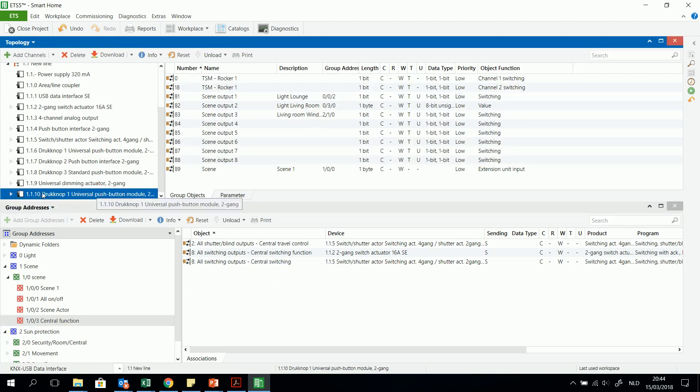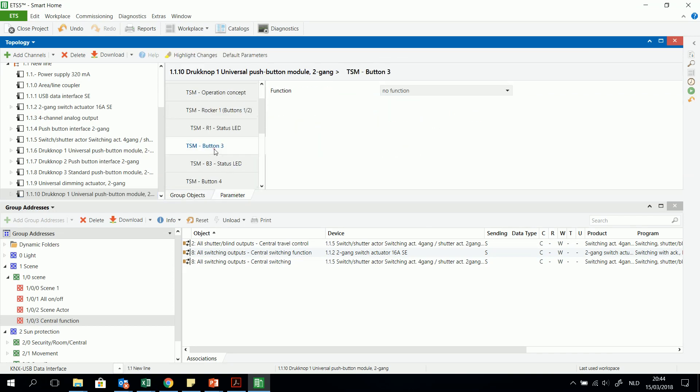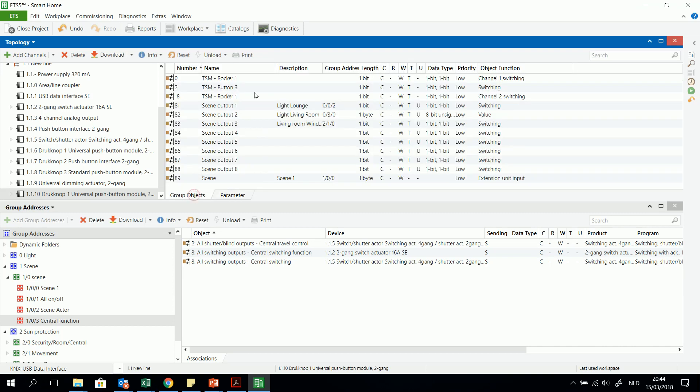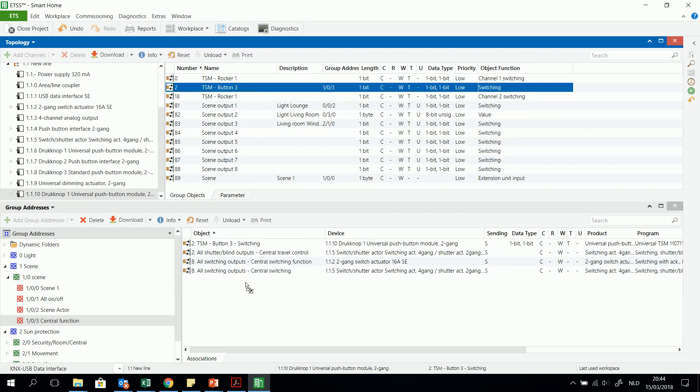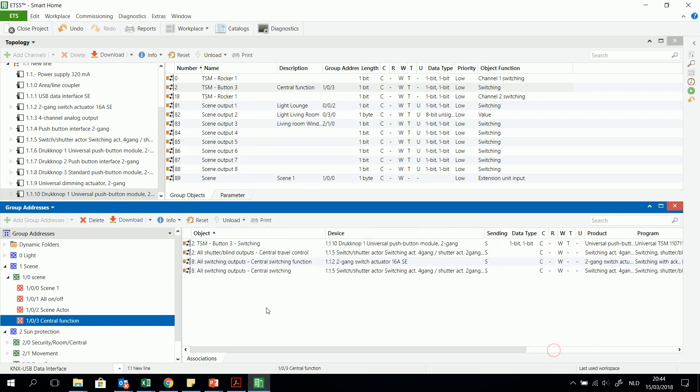And then I will take for example push button one. And I have to choose an output. I will take an output, for example three. No function. I will choose for switching. I can choose on or off or toggle on off. Then I have both. And then I can control those three central objects with only one button of one bit. And that's an example of how to program a central function.